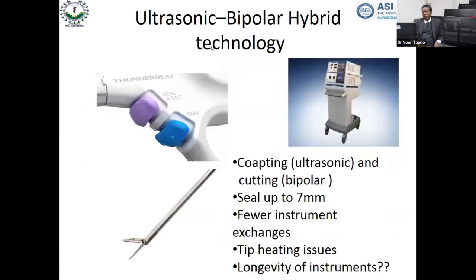Now, this is what I was talking about, this change that has come. Ultrasonic technology has now also introduced a bipolar technology within it. This is actually an Olympus machine. So what it does is the ultrasonic takes care of basically the coagulation of the coapting part, and the cutting part is actually done by the bipolar current.